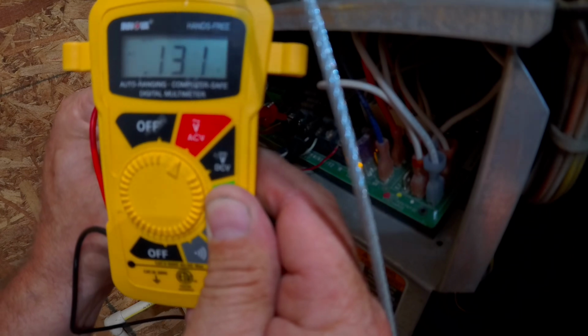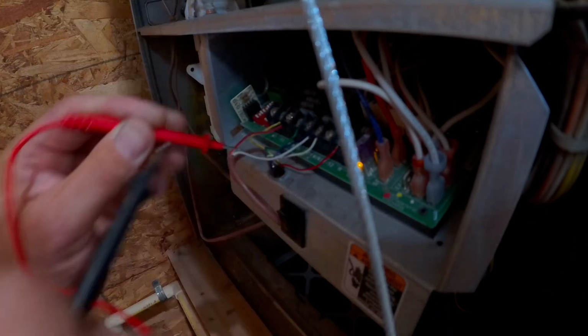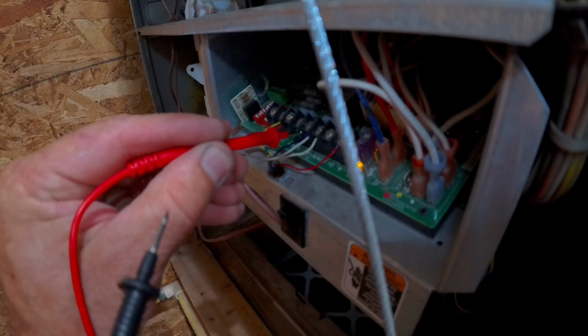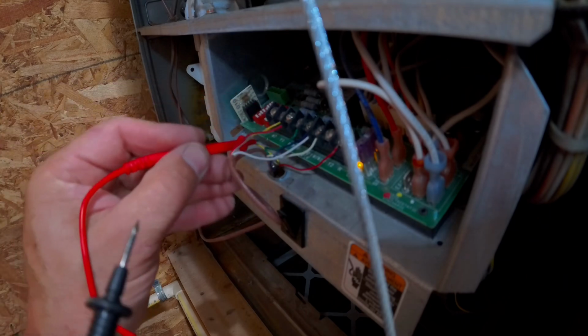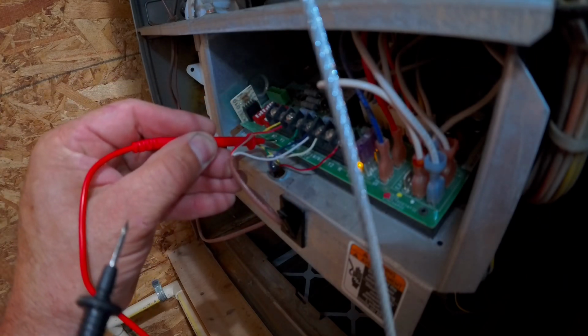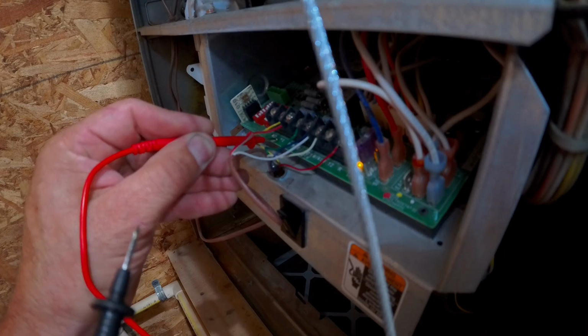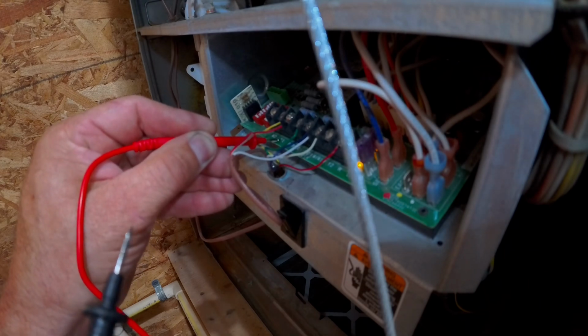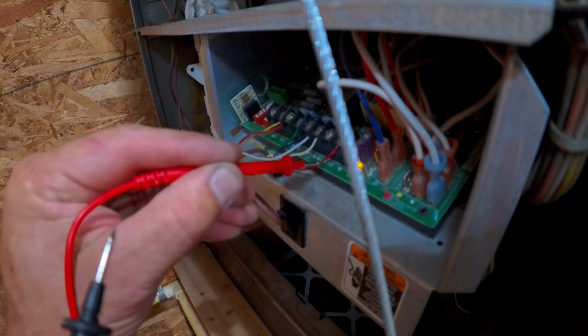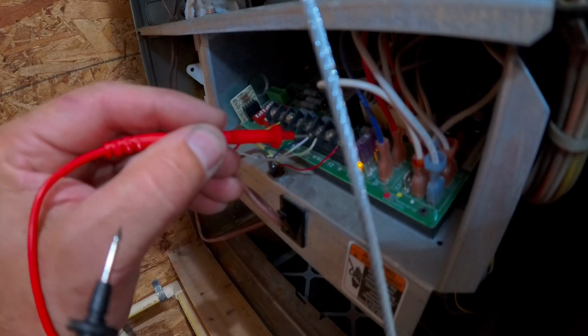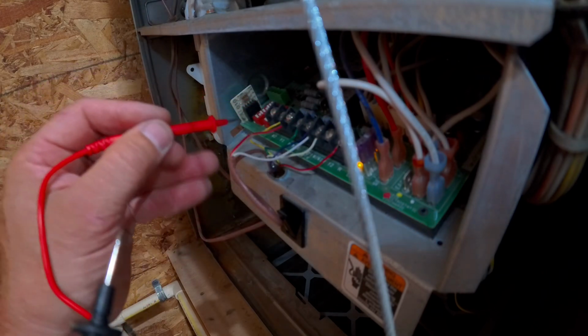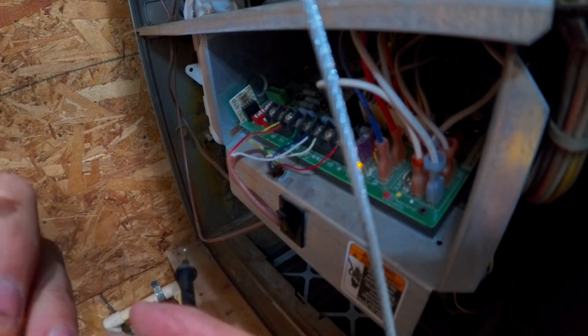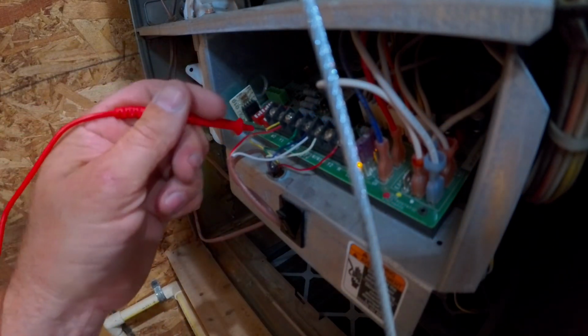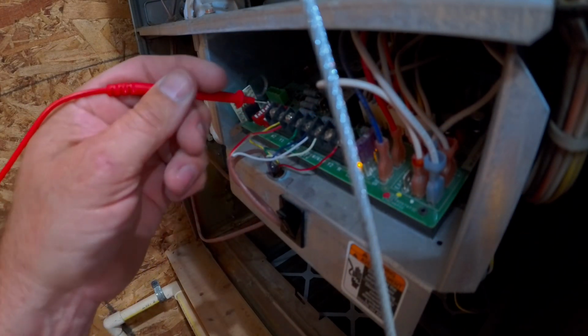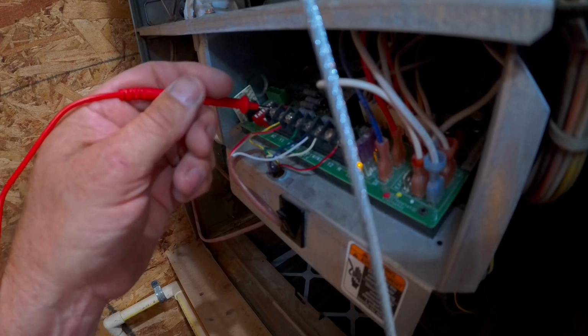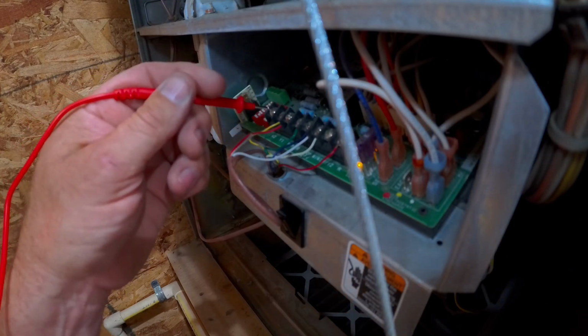So now, what about the air conditioning? Let's check that. Again, we're going to go from the C terminal, and now air conditioning is always Y1. We have Y1 and we have Y2, same thing. We have first stage of cooling, which is Y1, and we have second stage of cooling, which is Y2. There's nothing hooked to Y2, so we're not going to worry about it. So with that being said, Y1 is our first stage of cooling, so that's where our voltage should be, because the thermostat is now telling the air conditioning to turn on.